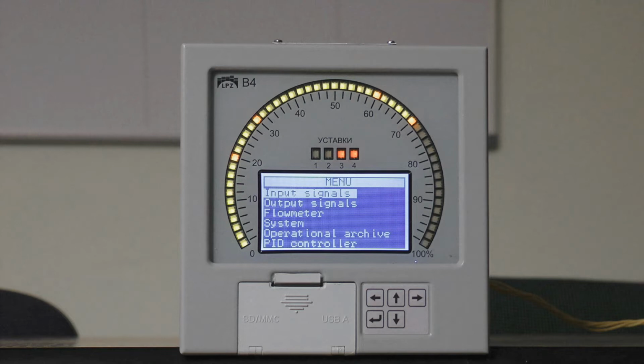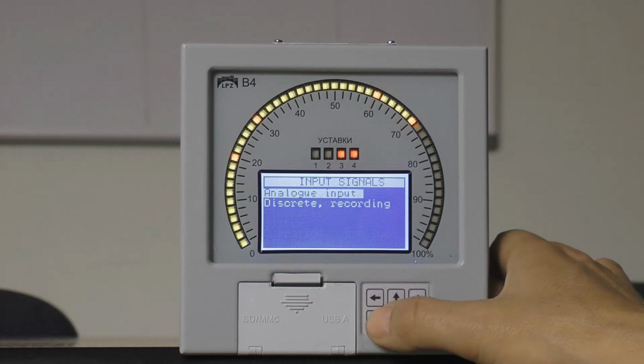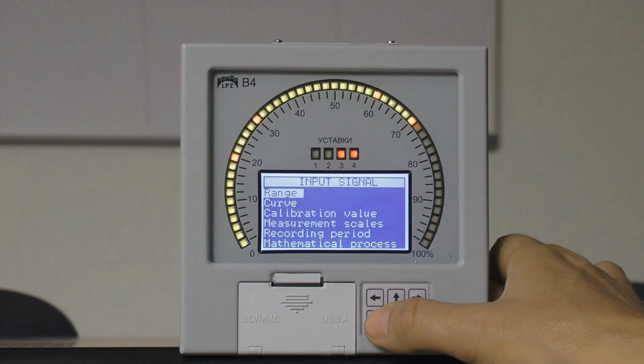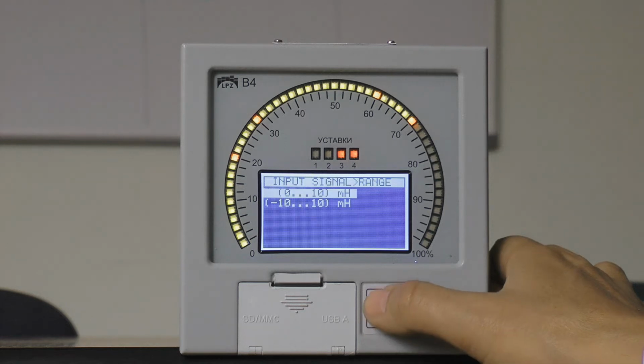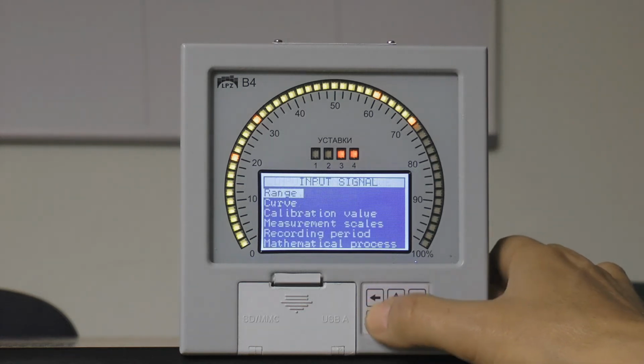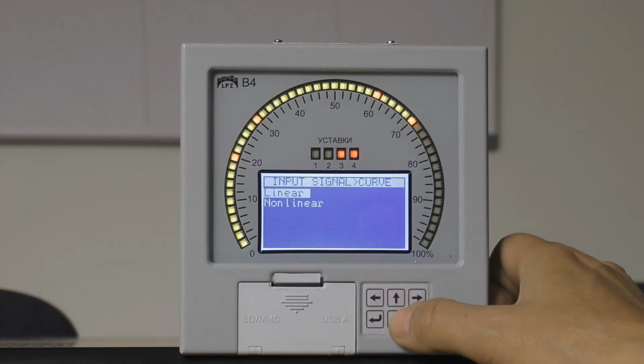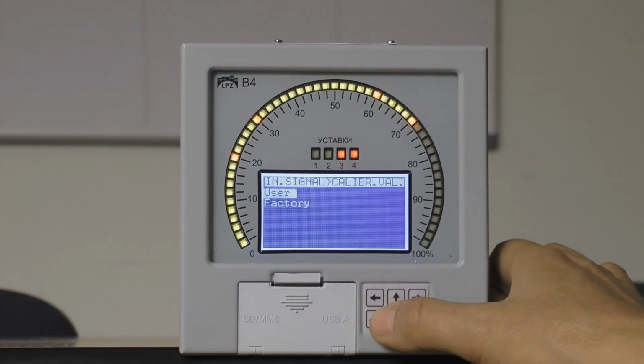Let's see the input signals menu. Input signals include analog and discrete input. Let's have a look at the analog input menu. In input signal, you can adjust range, curve, calibration value, and measurement scales, recording period, and mathematical process. I would like to have a closer look at range settings. It can be from 0 to 10 and from -10 to +10. Curve can be linear and non-linear. Calibration values can be factory and user's.